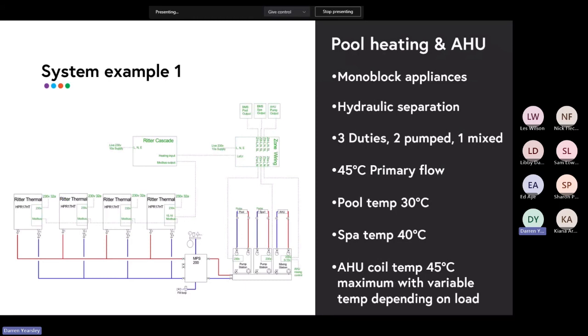And so with a 0 to 10 volt input on the mixing station, you can connect that along with your pump station. So we populate the buffer with 45-degree water. We pump that water directly out to the pool heat exchanger and to the spa heat exchanger. And then on that same manifold, we can have a mixing station where we can do variable water temperature. So yeah, that's the design in that system.